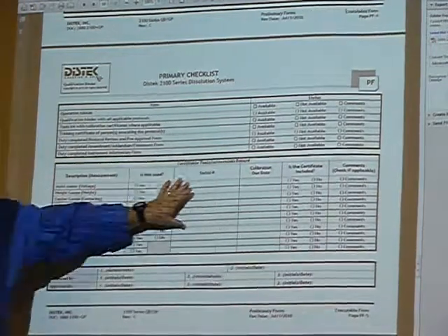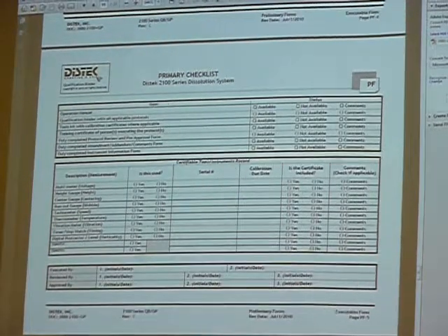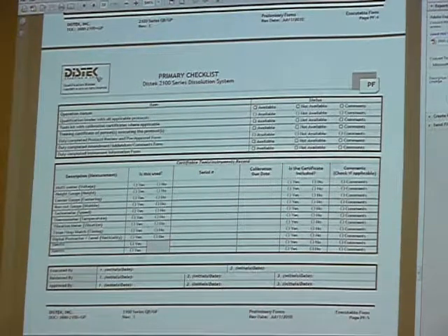This is where all your hand tools that you're going to be making measurements with are going to go on that page. Everything's traceable. I'm assuming regulatory commissions in your countries do the same thing. Here, they have to have the NIST traceables, which is National Institute of Standards traceability, for here in the States. We have to have everything NIST traceable, so everything we have has a certificate with it. It gets renewed on an annual basis.